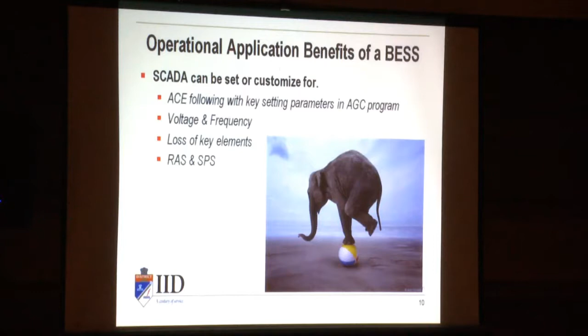The other part of the battery we plugged in allows us to set up parameters around voltage and frequency. Another key element is you can also put in RAS, special RAS schemes, so that when you lose elements on different parts of the line, the EMS will automatically send signals to the battery to absorb, push out, provide VARs for us, and do all kinds of applications.